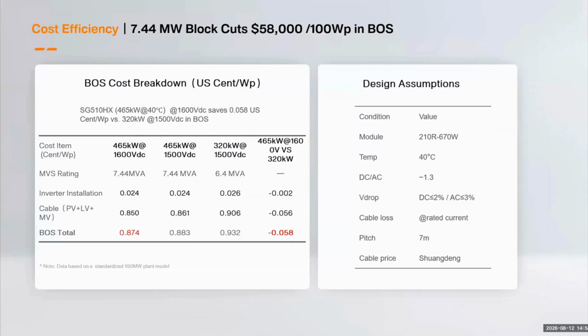This slide shows the system level benefit based on a standardized 100 megawatt plant model. A 465 kilowatt solution can save around 0.058 US cents per watt compared with a conventional 320 kilowatt solution. Most of the saving comes from cable optimization and installation. The important point is that inverter value should not be judged only by efficiency or purchase price. It also affects cable quantity, block design, and overall BOS cost.